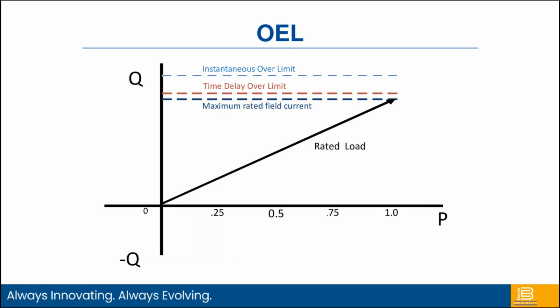Then it'll allow it to run there for a particular amount of time, and then I can pull it down to a medium limit after that time delay expires, and then pull it down to my continuous rating, or my low over excitation limit. So I can do up to 3 steps. We can also set them up for online and offline limits.